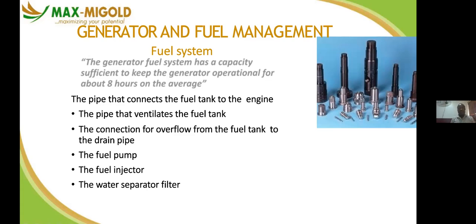The connection for overflow from the fuel tank to the drain pipe. You have to ensure that there is a connection, in case you overfill your tank, so there's an outlet where the excess can flow through and won't spill all over the area. You consider that. The fuel pump, the fuel injector, the water separator.